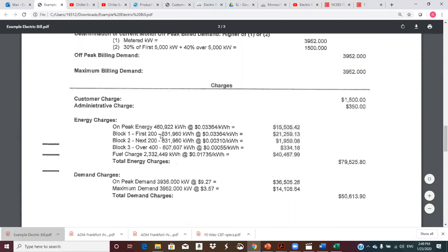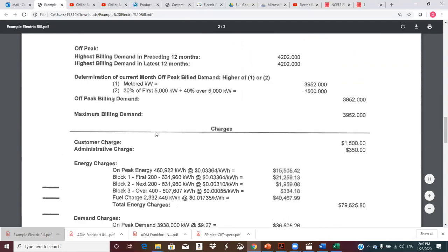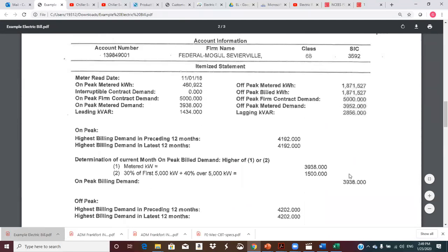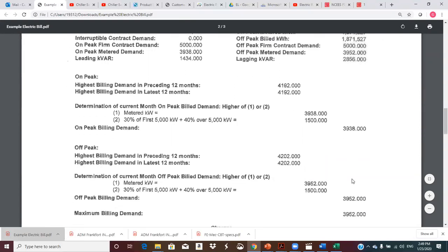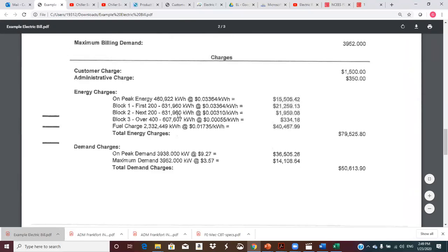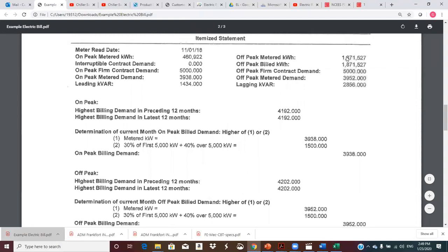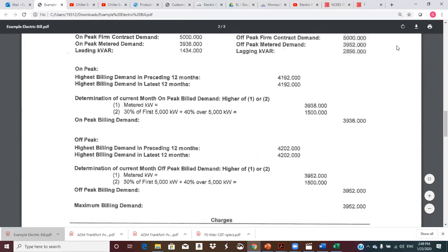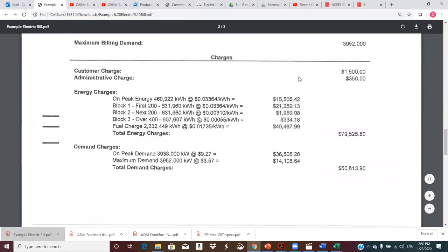So we got to do all that math now. We got to take, what was it? It's the on-peak demand. It's 3938 times 200 times the ratio of this energy divided by the total energy. So then you got to add them both together. You do all that math, and I checked this one time. It's correct. That comes out to 631,960 kilowatt hours. Okay? So this is the off-peak energy.